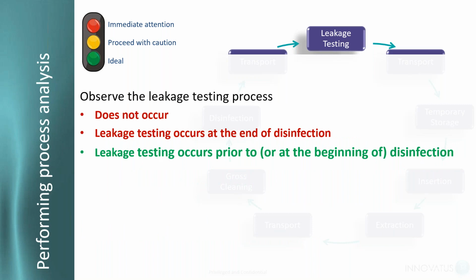So leakage testing does not occur, not a good idea. We talked about that. It occurs at the end of disinfection, also a very bad idea because you are now energizing a potentially fluid-invaded probe. As we all know, we're all technical on this call, or at least most of us are, and we know that liquid makes a wonderful conduit for electricity. And once we get liquid throughout that probe, we will start damaging the sensitive electronics in the connector, the control housing, or the tip. So we want to do the leakage testing prior to or at the beginning of disinfection.